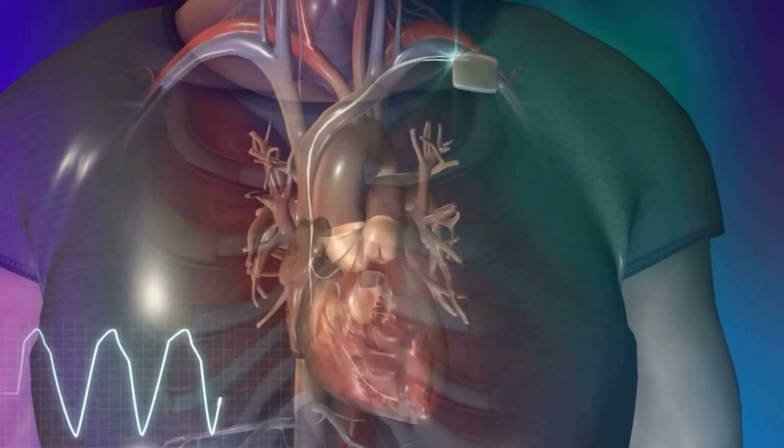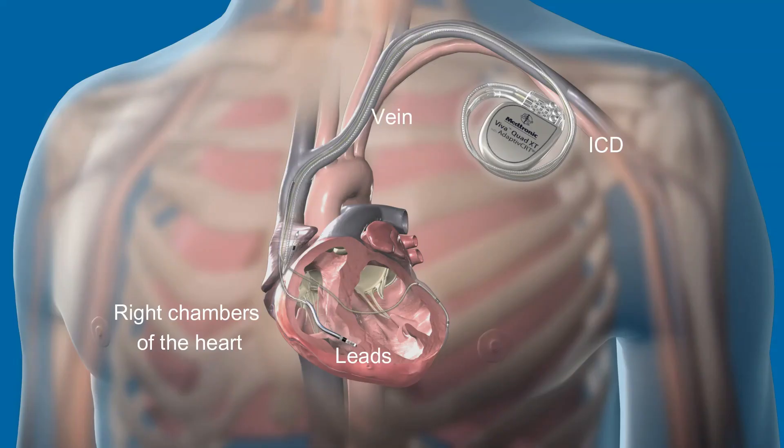ICDs are very similar in construction to the pacemaker. The ICD contains the electronic circuitry inside a titanium can. It is connected to the wires or leads through a plastic connector or header. The leads are passed through a vein to the right chambers of the heart. The lead is usually anchored in the apex of the right ventricle. Just like pacemakers, ICDs can be made to stimulate just the right ventricle with a single lead, the right atrium and right ventricle with two leads, or have three leads to stimulate the right atrium, right ventricle, and another lead present on the walls of the left ventricle.